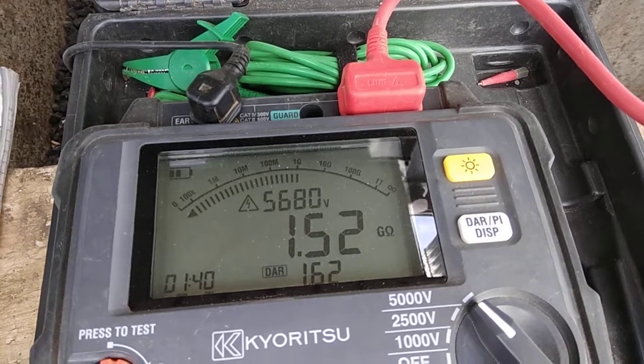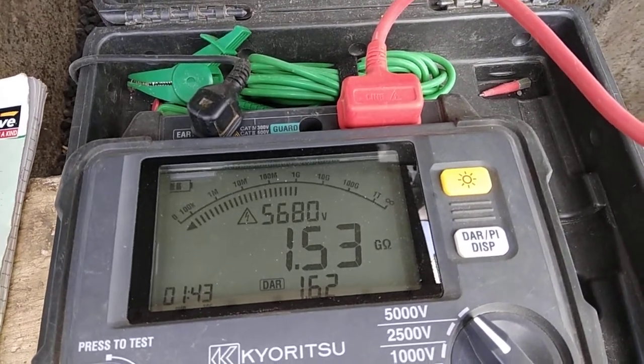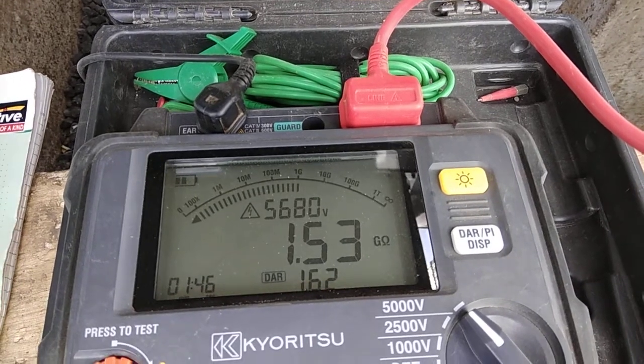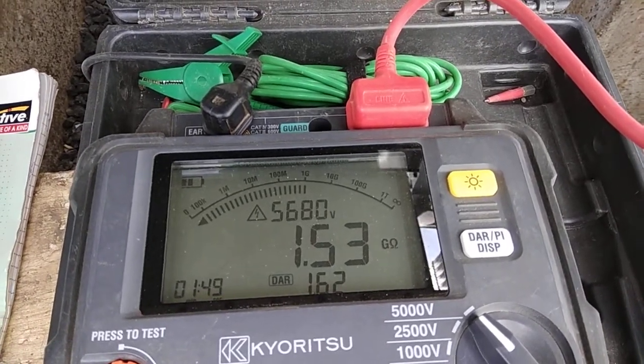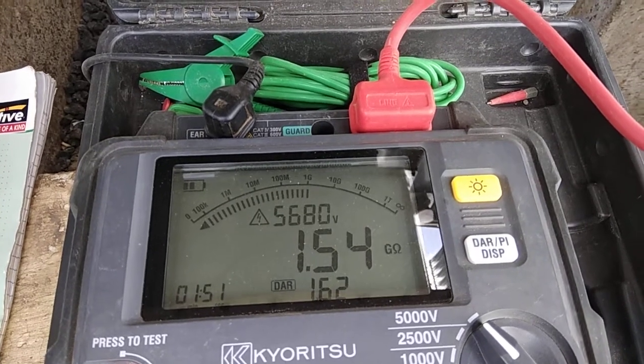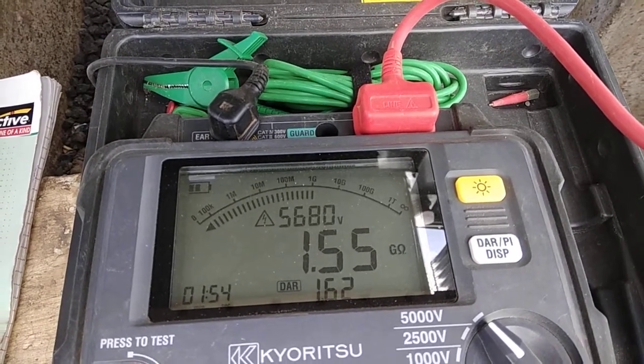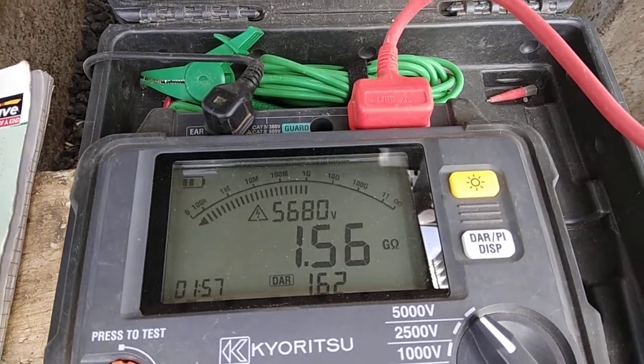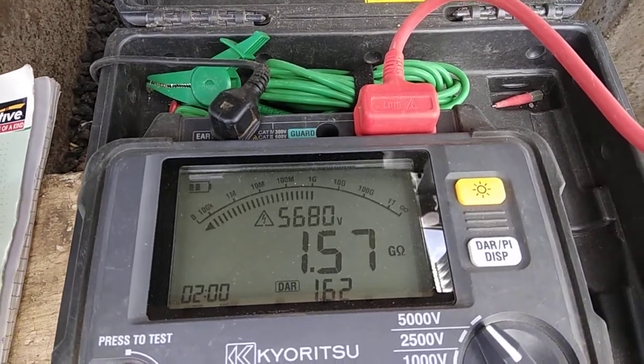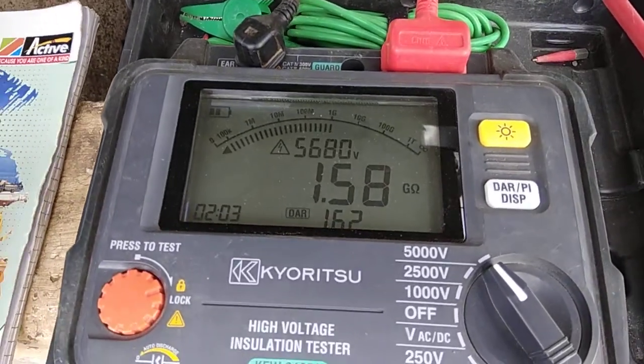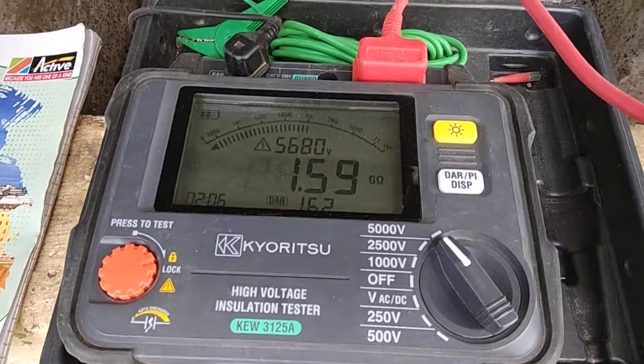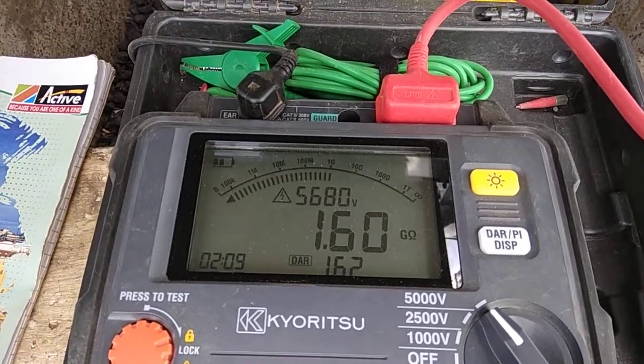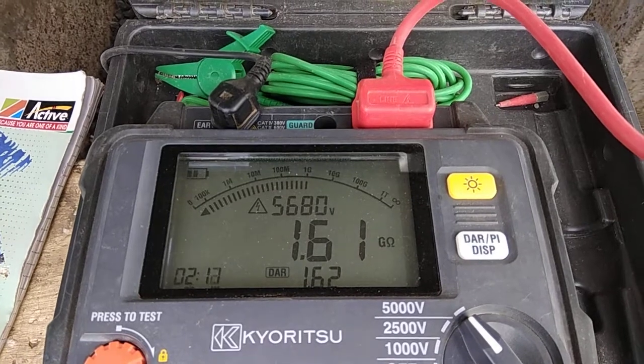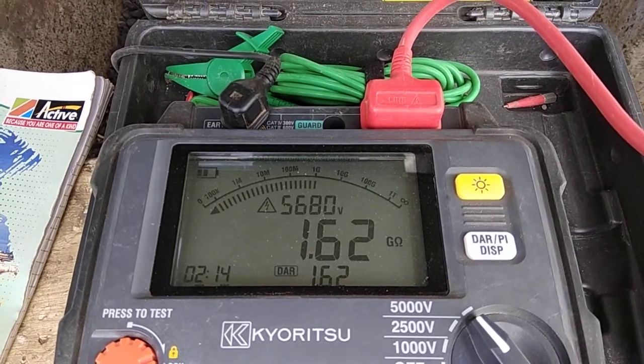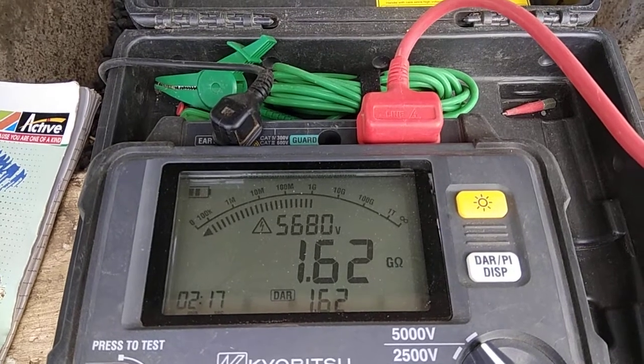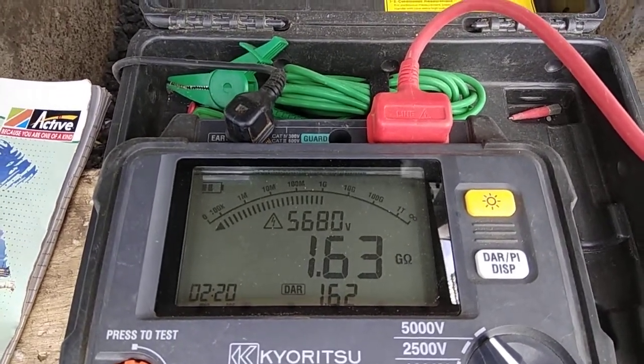After 10 seconds, it starts decreasing, and by 1 minute it's completely eliminated from the system. So the effect of the charging current remains only for 1 minute. So when we are performing DAR, we eliminate the charging current because it is the ratio of the 1 minute to 15 seconds. Coming back, the second thing is the conductive current. Every insulator has a degree of conductance, and that's why the conductive current always remains in the circuit, and this indicates the real quality or real standard of an insulation.